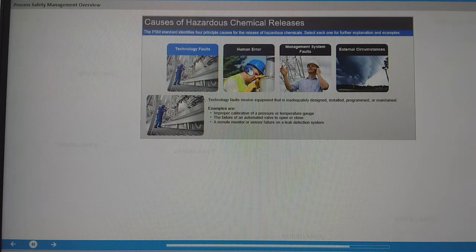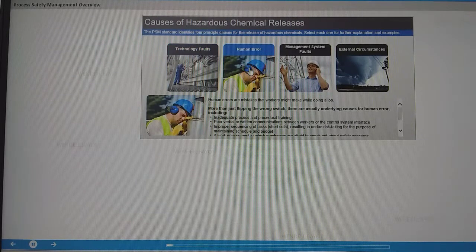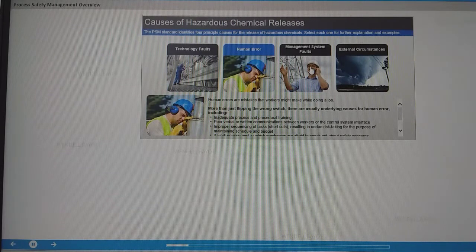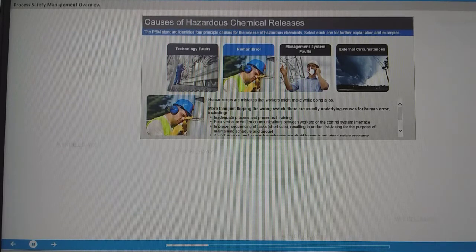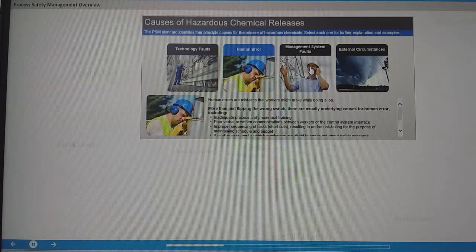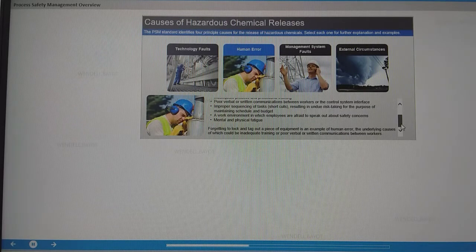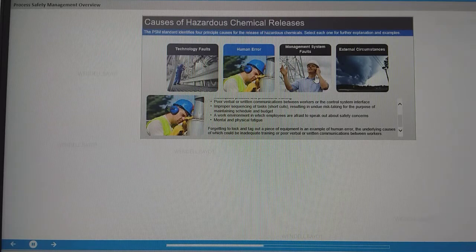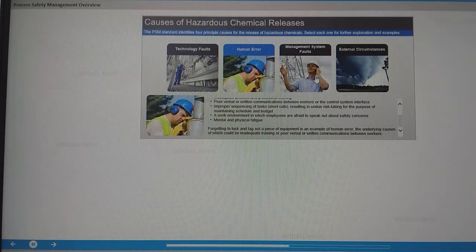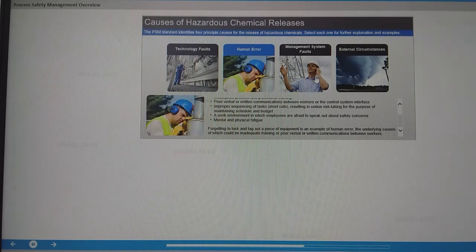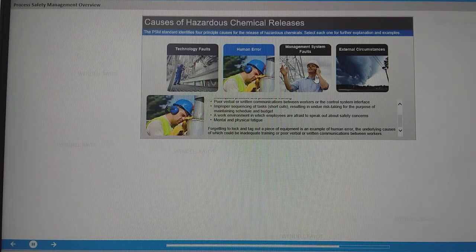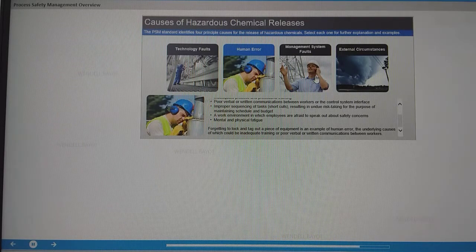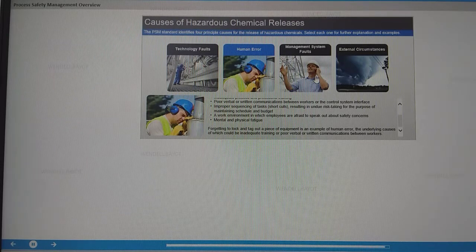Human errors are mistakes that workers might make while doing a job. More than just flipping the wrong switch, there are usually underlying causes for human error, including inadequate process and procedural training, poor verbal or written communications between workers or the control system interface, improper sequencing of tasks, shortcuts resulting in undue risk-taking for the purpose of maintaining schedule and budget, a work environment in which employees are afraid to speak out about safety concerns, and mental and physical fatigue. Forgetting to lock and tag out a piece of equipment is an example of human error, the underlying causes of which could be inadequate training or poor communications between workers.